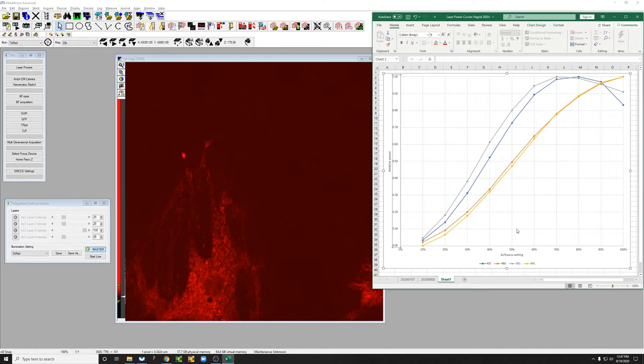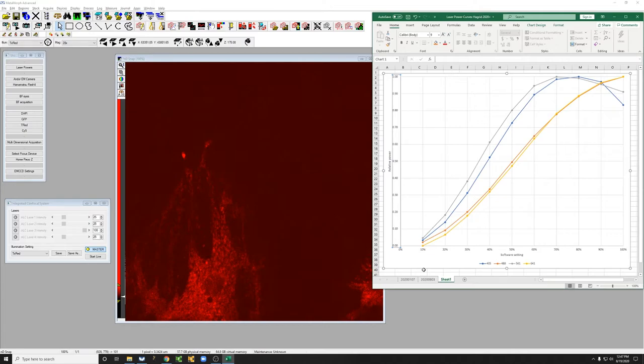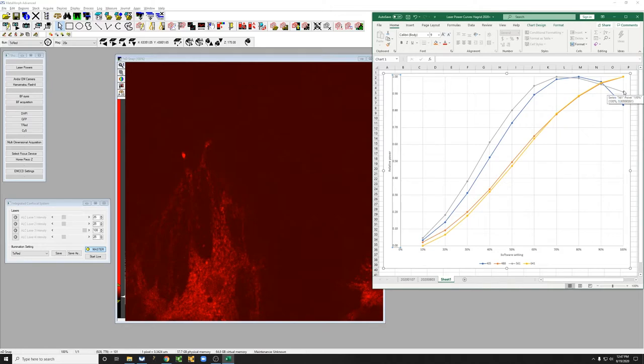you can go through the x-axis of this curve and see what the relative power is going to be at the sample. You can see that we started at 25% with the 561 laser, roughly there at 0.3. And then when we went to 100, we actually were not at the maximum. The maximum is at 70.